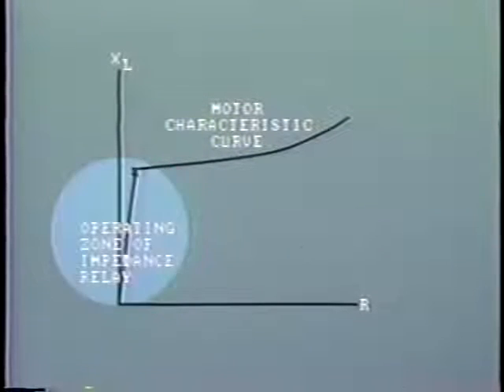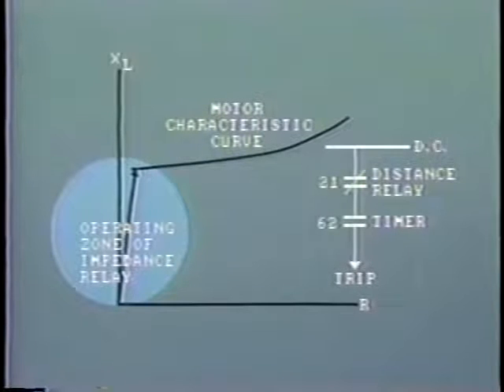So, how can we get the motor to start at all? Well, a permissive, normally open contact operated by a timer is connected into the trip circuit. This contact will only close after the specified number of seconds for normal startup. Actually, the timer is operated by AC current, so that its operating time will slow down if there is a reduction in bus voltage with consequent longer startup times. When the permissive contact closes, the impedance relay is now able to operate normally and trip for low impedance due to a fault.